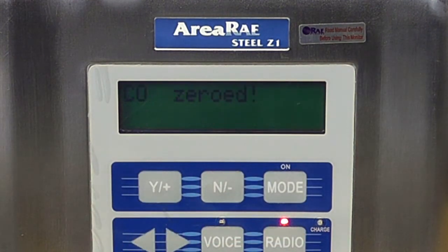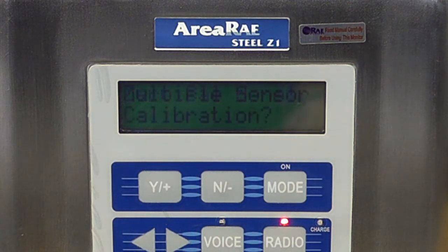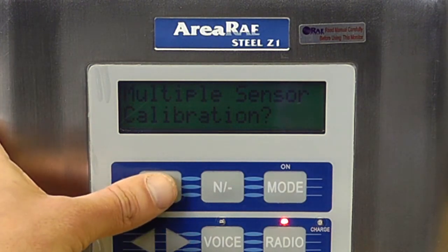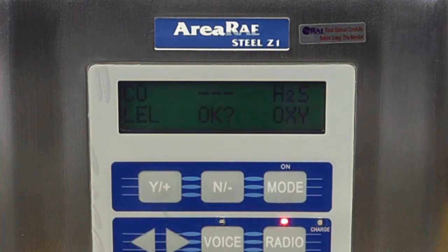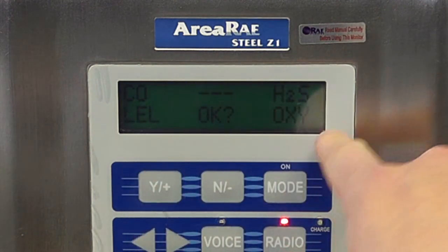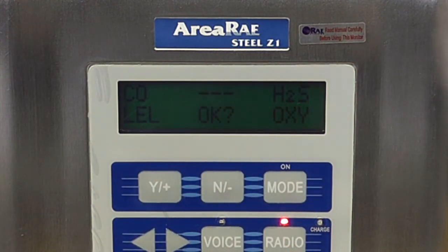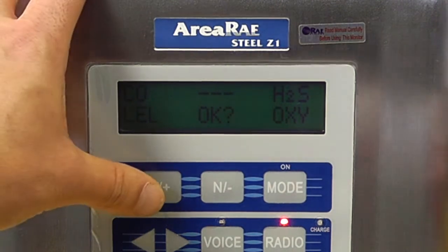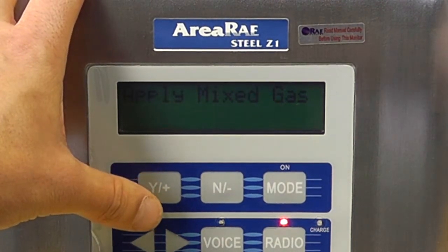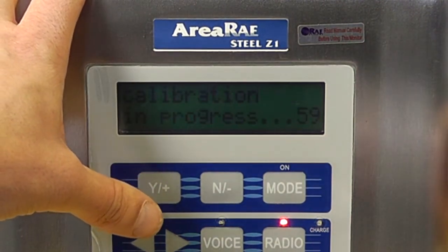This will zero each of the sensors and give us a 20.9 level on our oxygen. So we can see that's all done successfully. Now we can continue to a multiple sensor calibration. So we say yes, and this will calibrate CO, LEL, H2S and oxygen. We happen to have a can of 4 gas mix here.